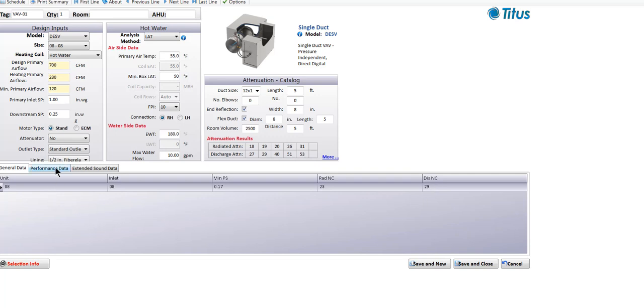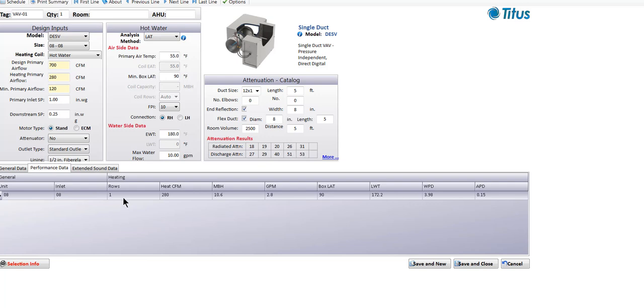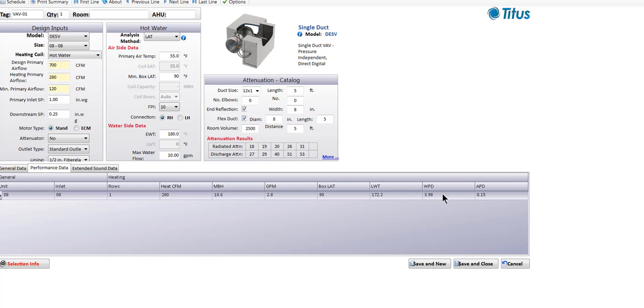Looking at the detailed results on water coil performance: it's a one-row coil with 280 CFM going through during heating mode, giving us 10.6 MBH. The GPM water flow is 2.8 gallons per minute. The box leaving air temperature is 90 degrees Fahrenheit as requested. Our leaving water temperature is 172.1 degrees, our water pressure drop is 0.98 feet, and our air pressure drop of the coil alone during cooling design airflow is 0.15 inches.